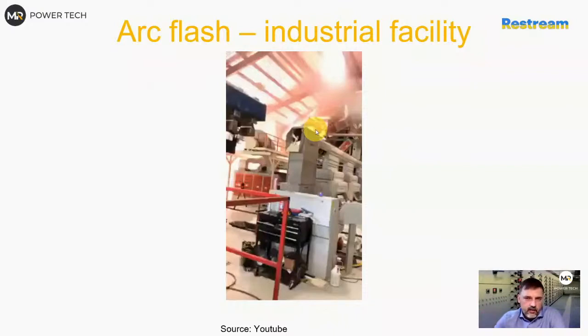There are a lot of things like this, and it's very hard to judge just by looking - that's why I do a lot of calculations. If you just look at it, it's just equipment as equipment, but there might be two identical switchgears in the same facility with very different results, to be honest. It happens often in my projects that people just see this panel is 2 cal and the other is 25, and I have to explain why. That's why the full report always matters.